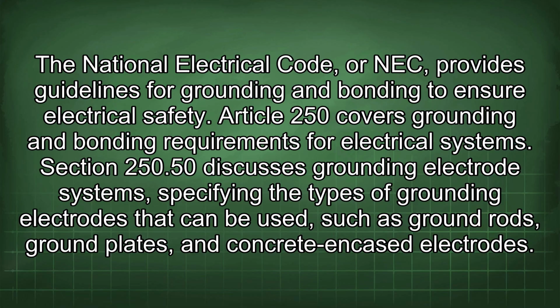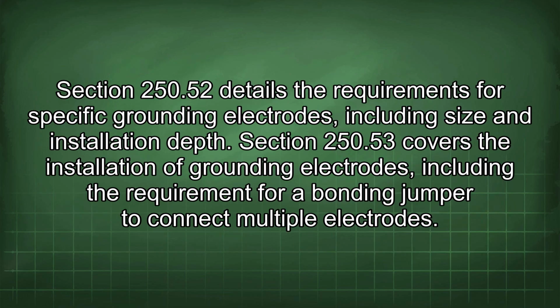Section 250.50 discusses grounding electrode systems, specifying the types of grounding electrodes that can be used, such as ground rods, ground plates, and concrete-encased electrodes. Section 250.52 details the requirements for specific grounding electrodes, including size and installation depth. Section 250.53 covers the installation of grounding electrodes, including the requirement for a bonding jumper to connect multiple electrodes.